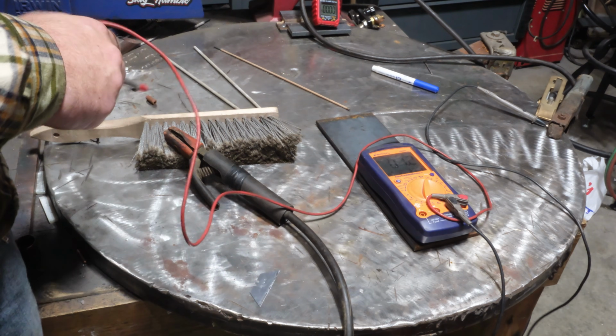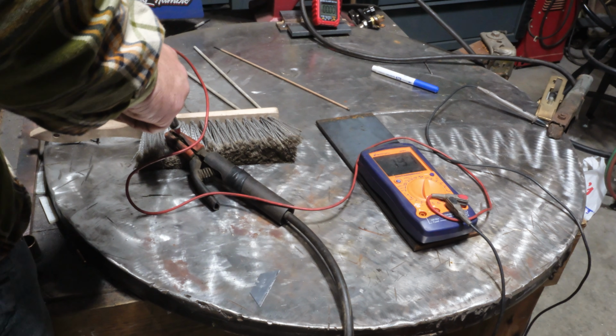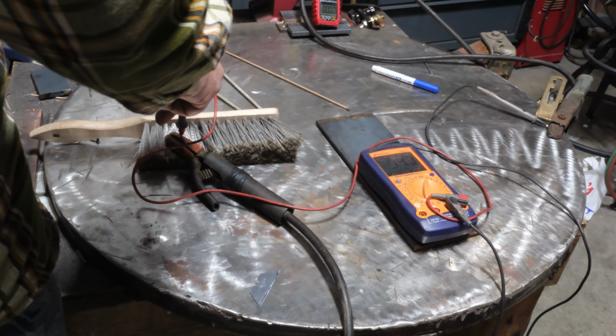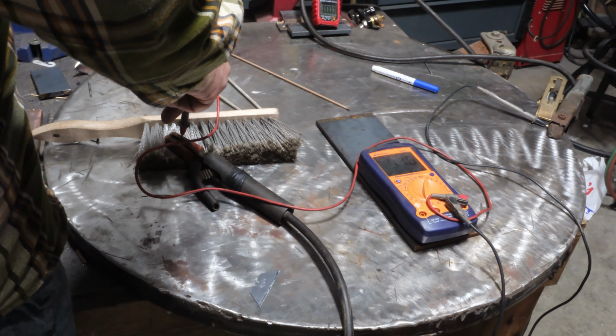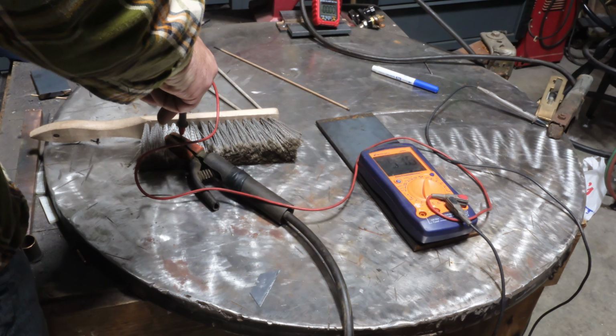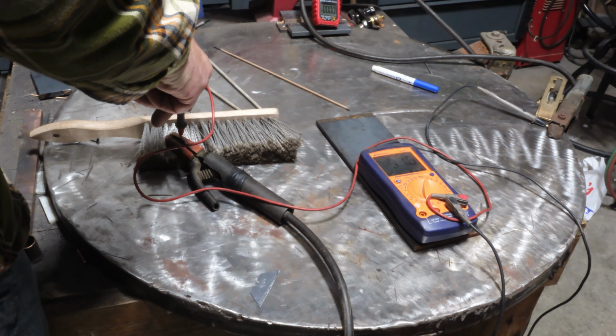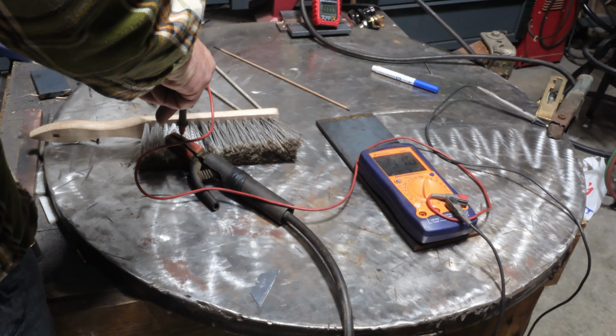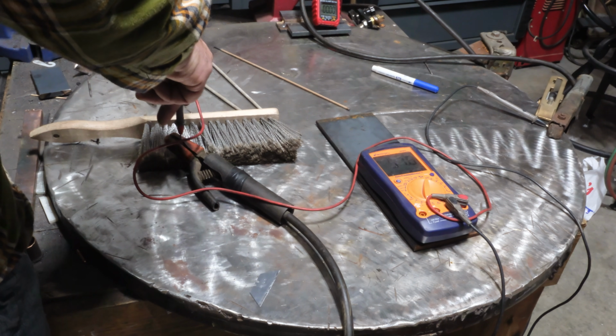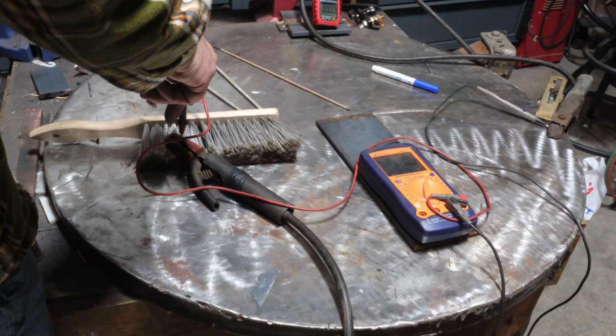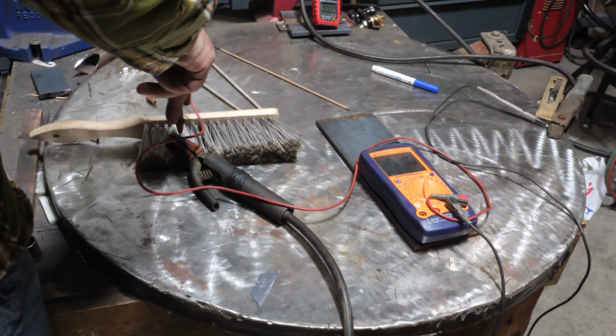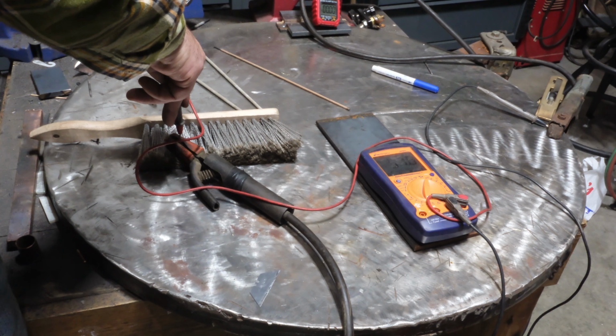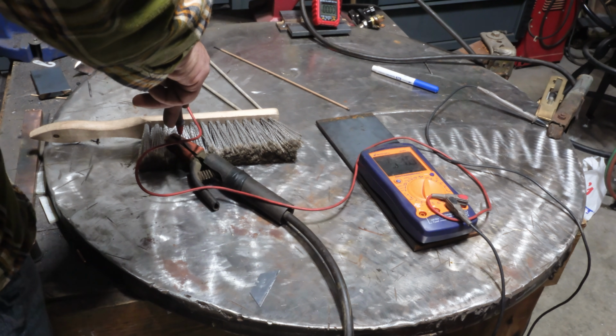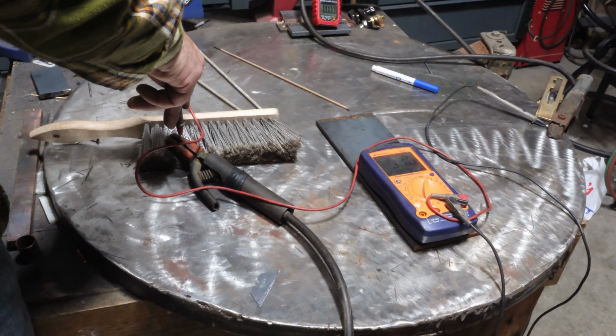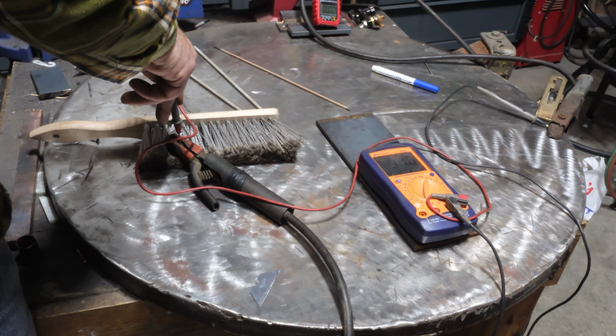Let's take a look at what its resting open circuit voltage is. 57.5, that's pretty interesting. Most stick welders of this era would be up in the 80s to 100 volts. So the way this is set up, and maybe it has something to do with that capacitor in there, the voltage is a little bit less. That isn't necessarily a bad thing. It'll probably be a little bit harder to strike an arc with this unit than maybe a buzz box of the same vintage, but let's take a look.